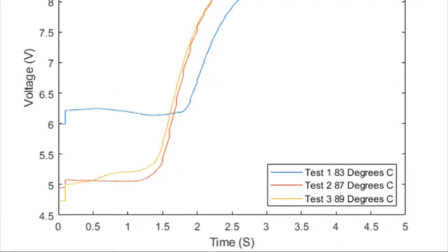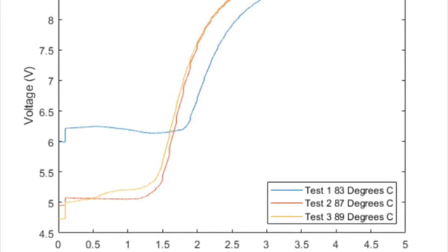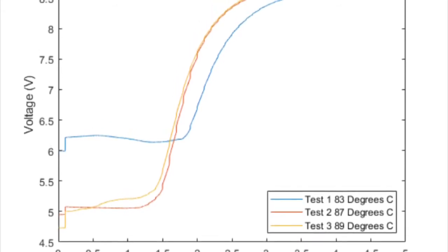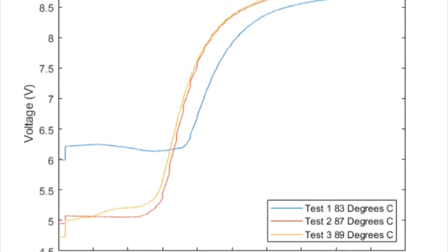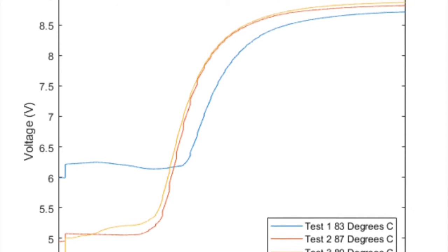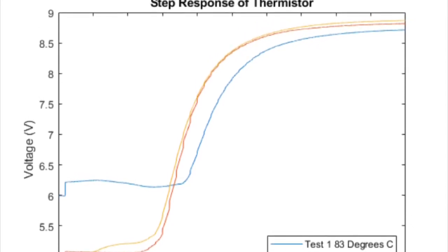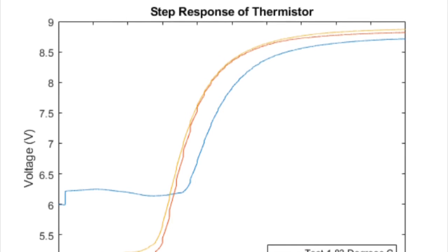So for our dynamic calibration analysis, we tested 3 different temps, plunged into the boiling water. We recorded the steady state that was reached for each, calculated a temporal step response plot, performed a least squares analysis, and then determined the time constant for each temperature recorded, and then averaged them to be about 1.5.